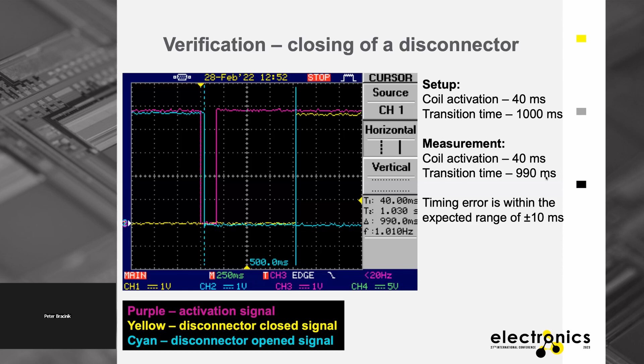This is for the disconnector. Coil activation was 40 milliseconds, transition time was set to 1000 milliseconds. There was a signal to close, so it takes some time, and then the open signal changed to 0 and the closed signal changed to 1. It took about 40 milliseconds for activation and approximately 990 milliseconds for transition time, confirming correct operation.